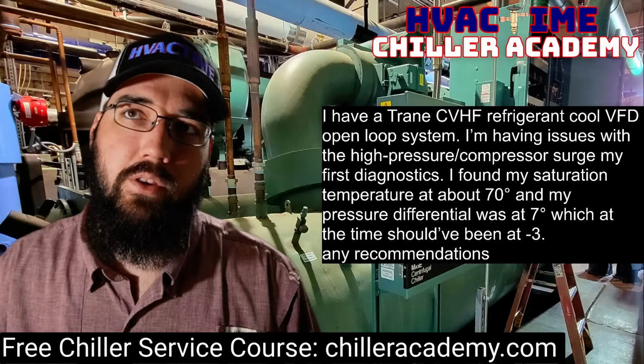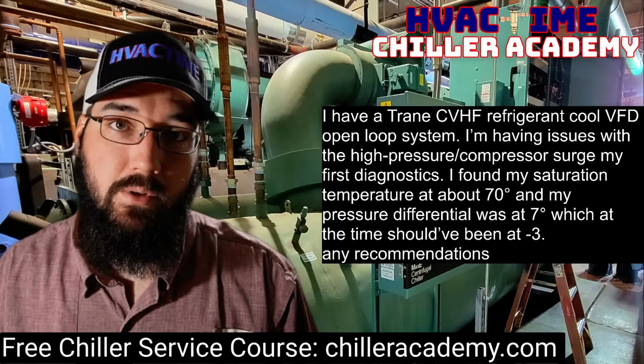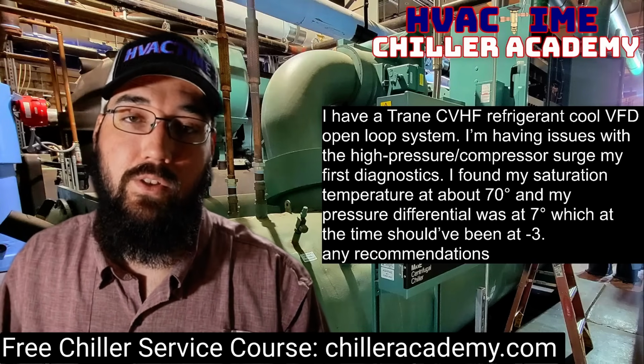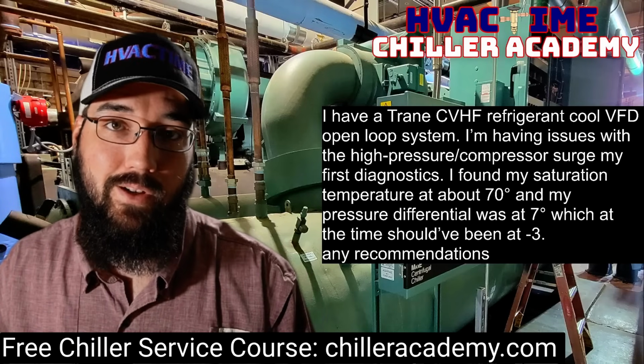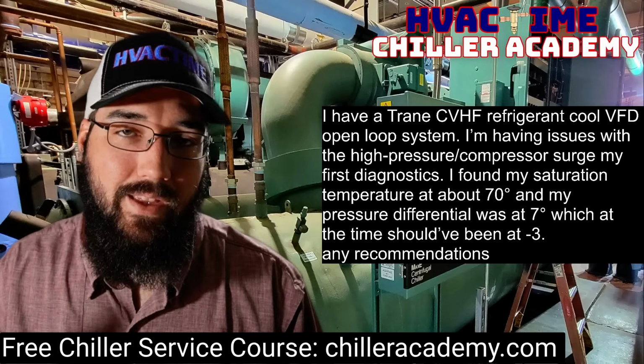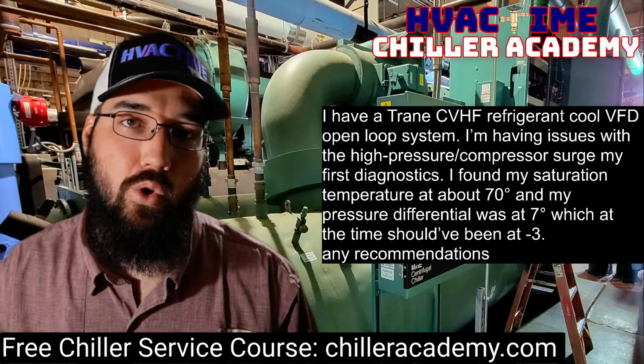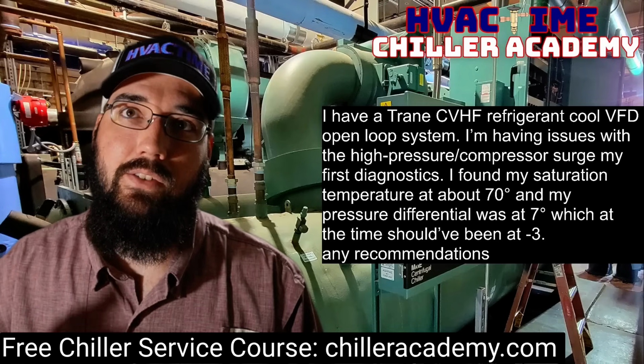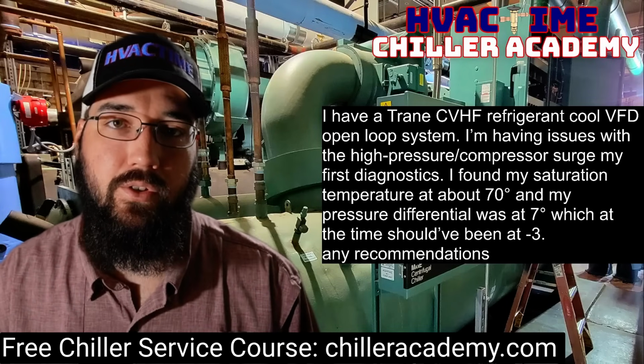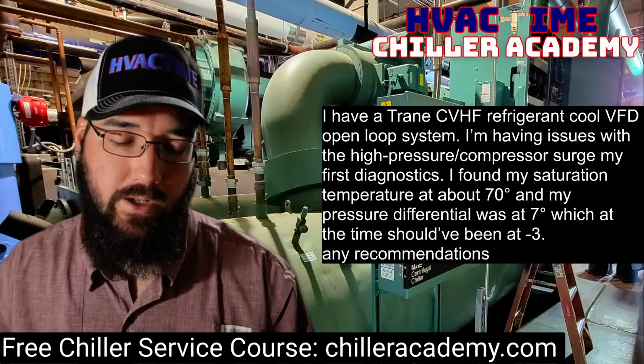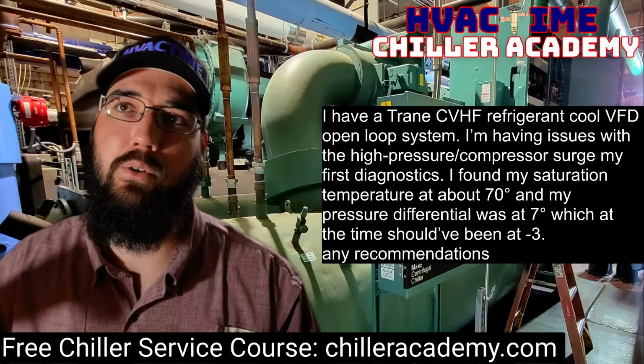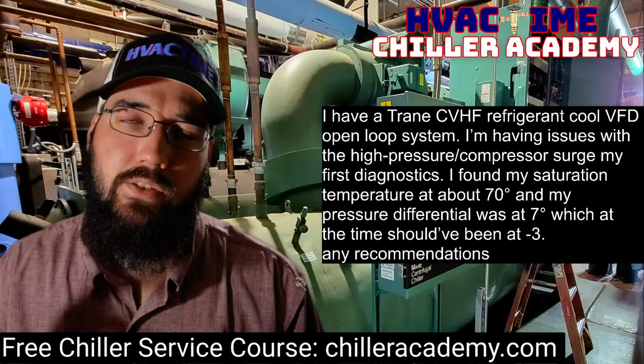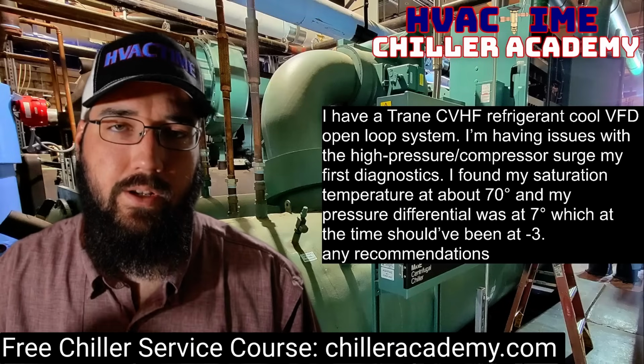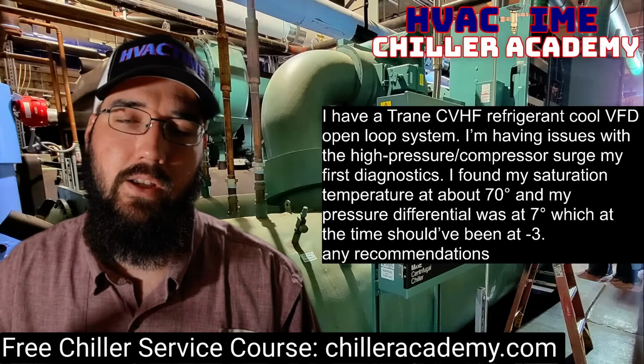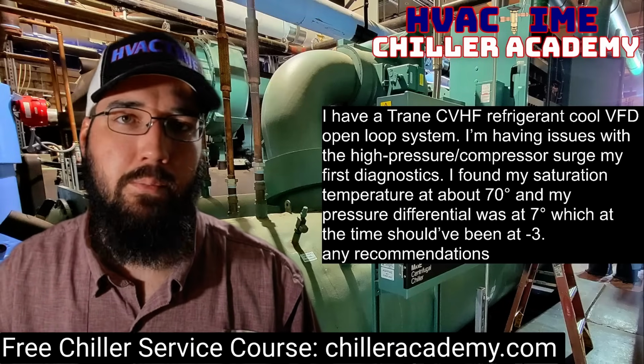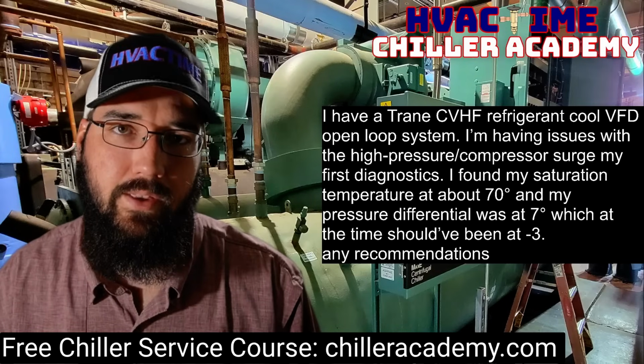So going the route of, okay, we need to get a purge system online. In terms of recommendations, that would be one of my next steps. I do want to verify, one, is the onboard purge working correctly? Is the temperature sensor on the suction line for that Trane system, being the Earthwise purge, on the purge unit actually reading correctly? Because that'll have a huge impact on whether or not we're pumping out correctly. So did we verify that sensor?